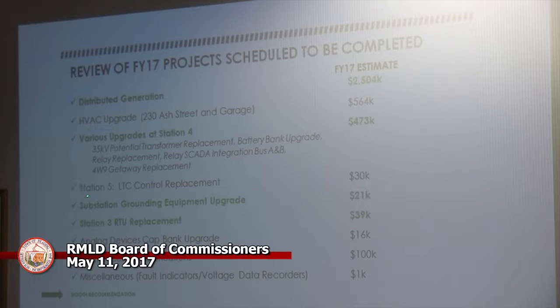Out of that, Station 5's LTC control replacement—we had a problem at that substation with the transformer LTC, that's all fixed. Substation grounding equipment upgrade is all done. This station RTU is the communication device between Station 3 and the local control room, or SCADA at the control room.